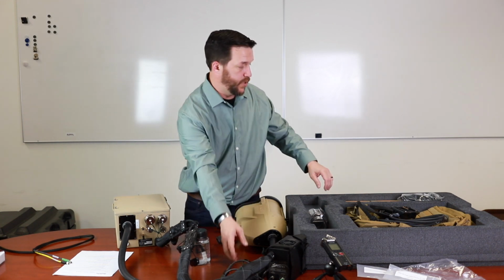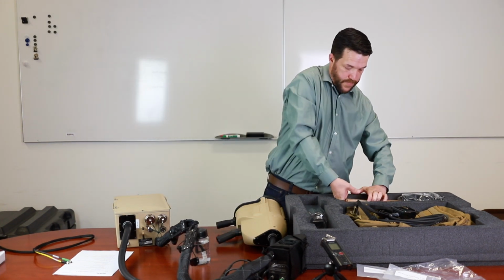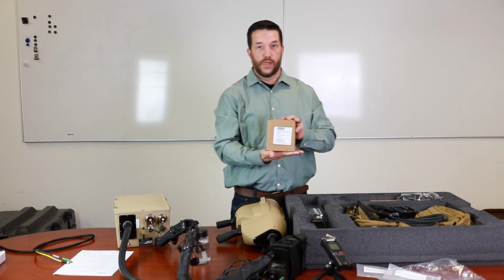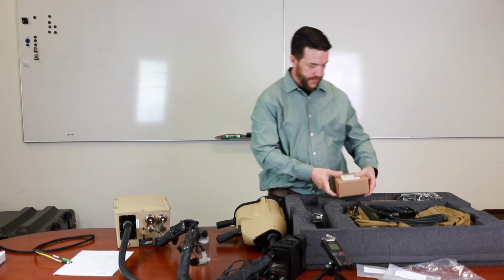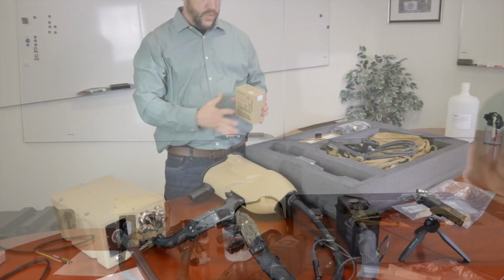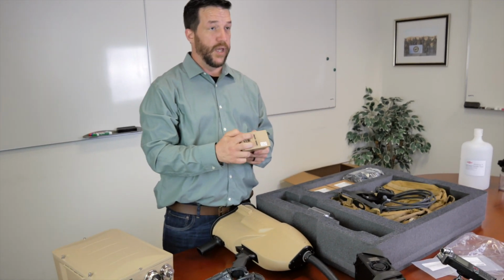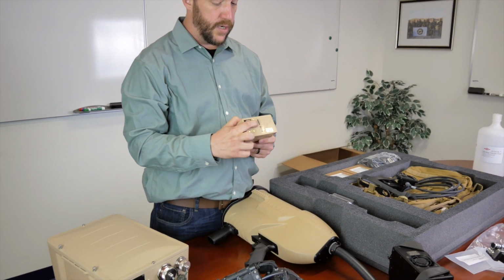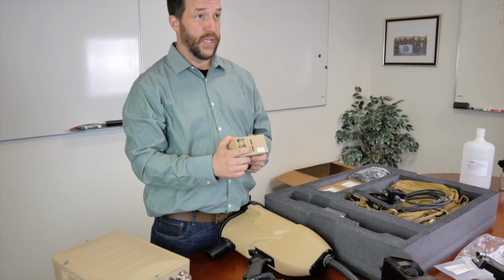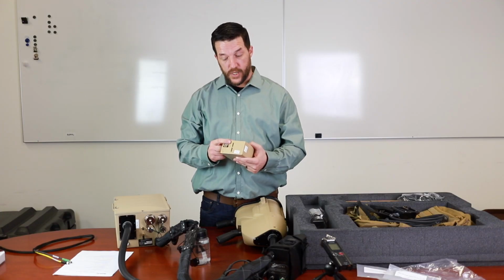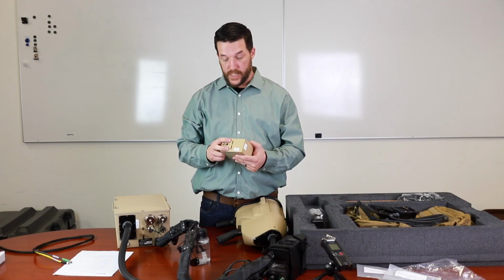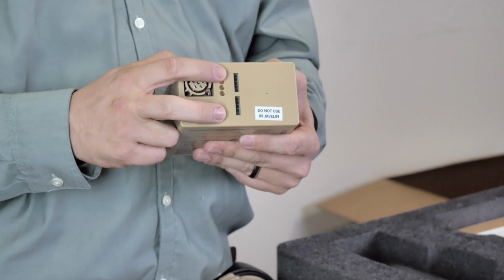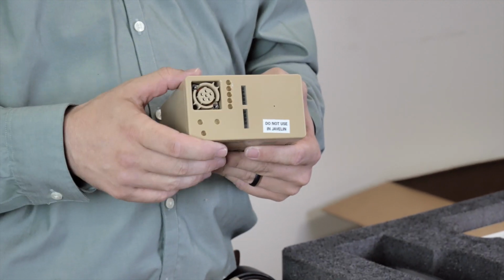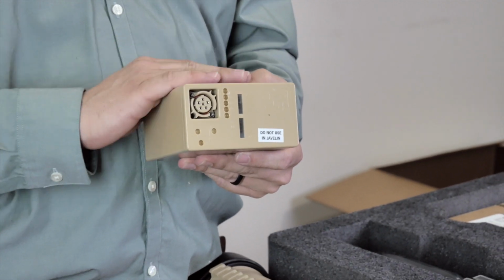What we'll do now is grab one of your batteries that's also in the shipping case. What you want to pay attention to on the battery is our displays. There are indicators of how charged your battery is. What you want to make sure is that the difference between these two cells is equal. One bar difference is fine. Anything more than that might indicate a bad cell in your battery.